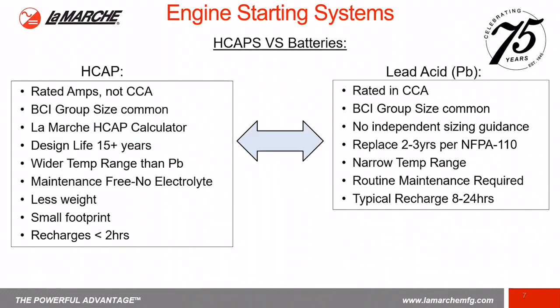Some differences between the hybrid capacitor and batteries themselves. Hybrid capacitors are rated in amps, while the lead acid batteries that are used in the engine starting market are rated in cold cranking amps. They both follow a common group size. However, with the lead acid, there really isn't an independent sizing guidance on how to size lead acid batteries for engine starting applications. For the hybrid capacitor, LaMarche has developed a calculator to size it based on certain parameters on your generator.